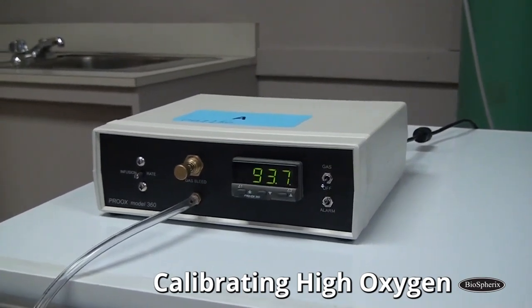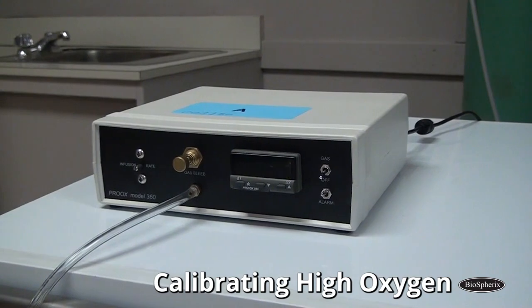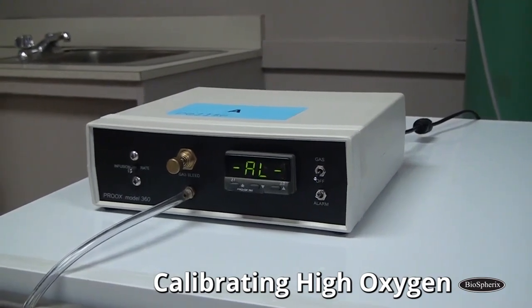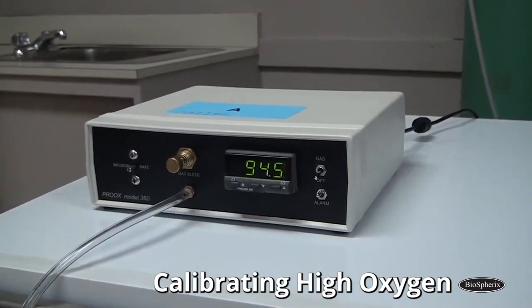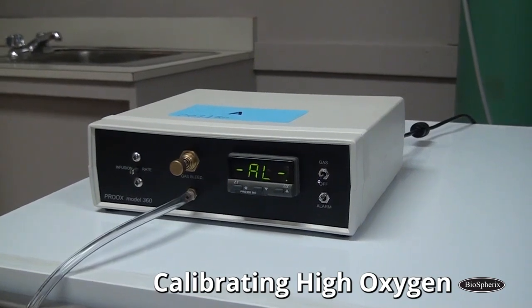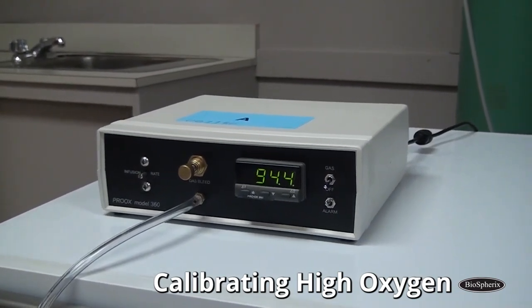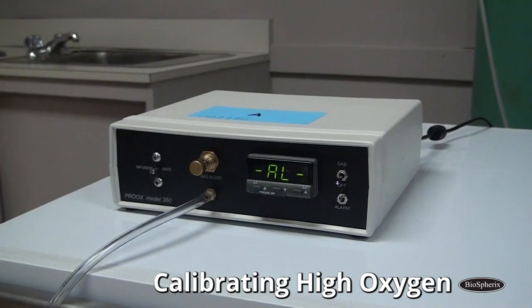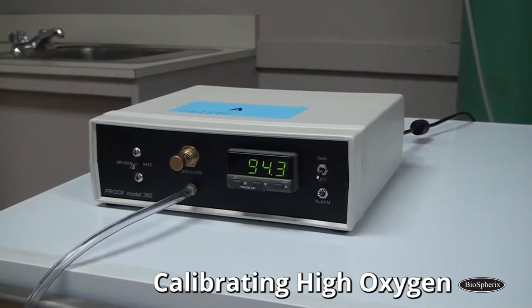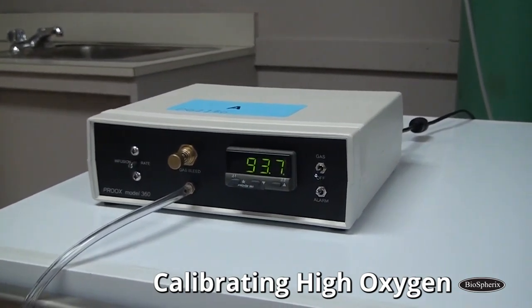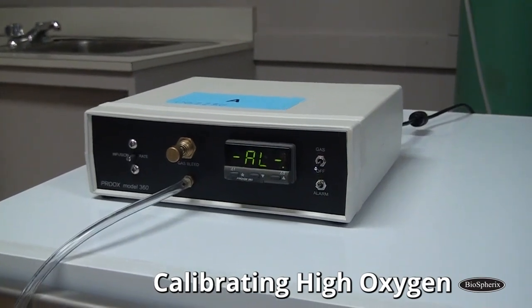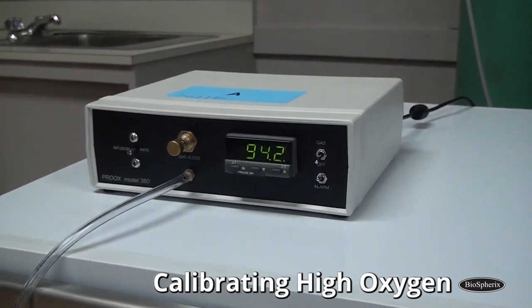It's not quite as accurate as if you were going to use room air as your span value. But the idea is, if your set point is above room air, you always want to calibrate your 0 below your set point and your span above where your set point is. So if your set point is set for above room, 30, 40, 85, anything, you have to have a lower set point for 0 and a higher set point for your span.